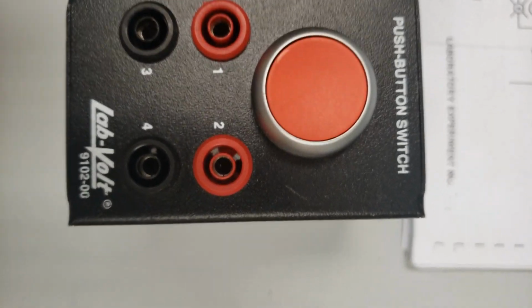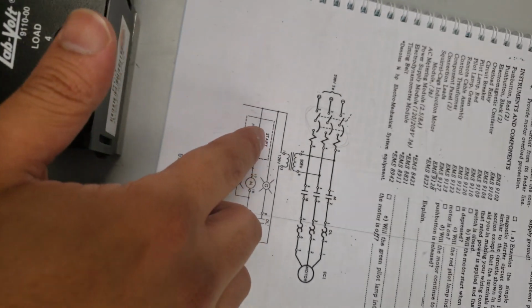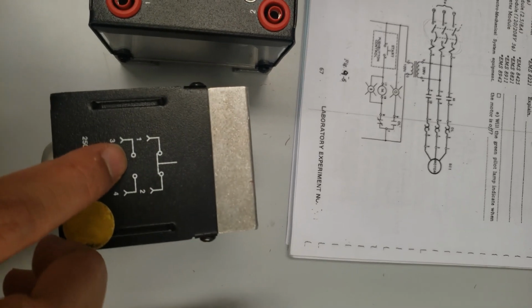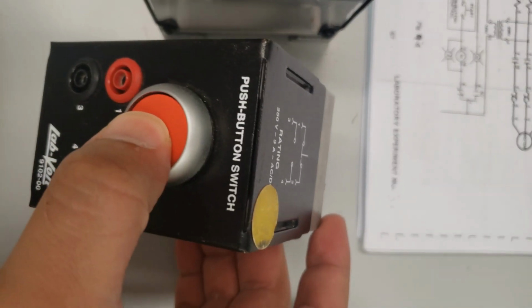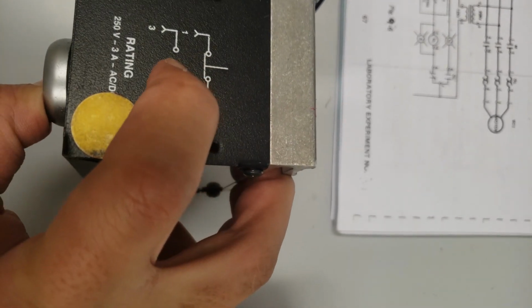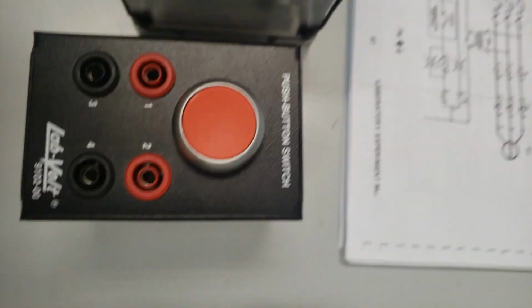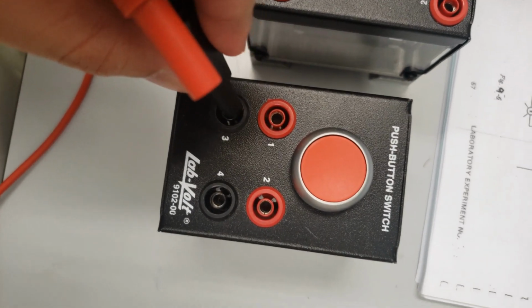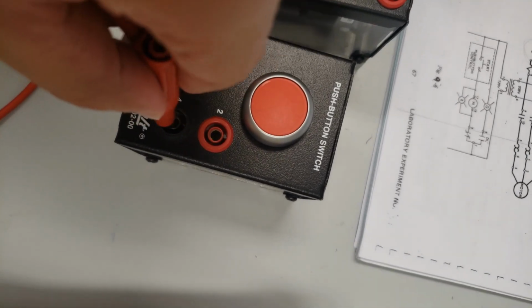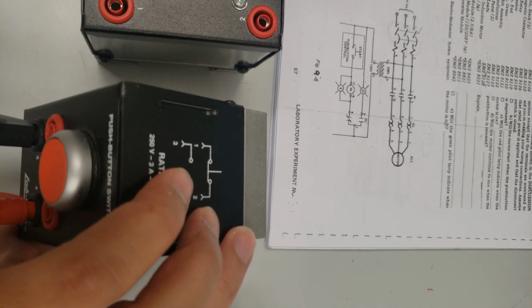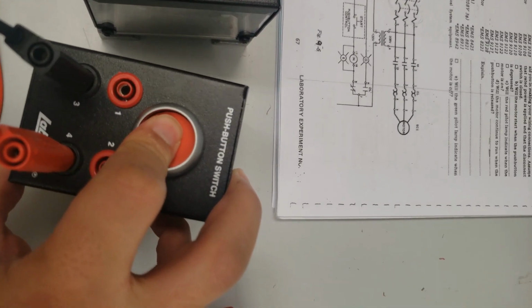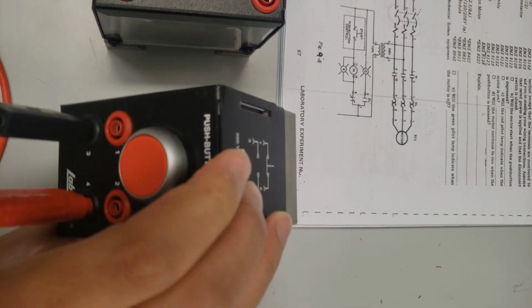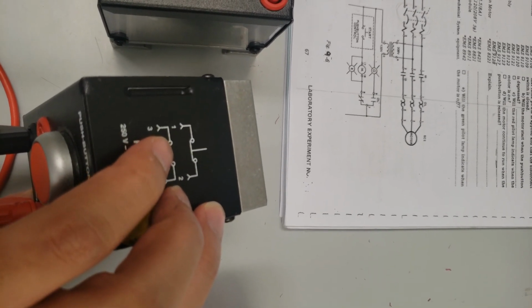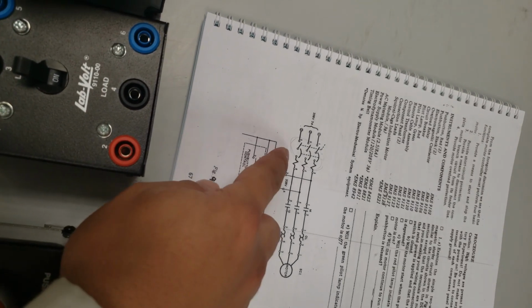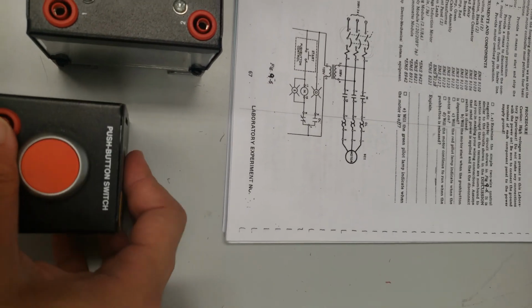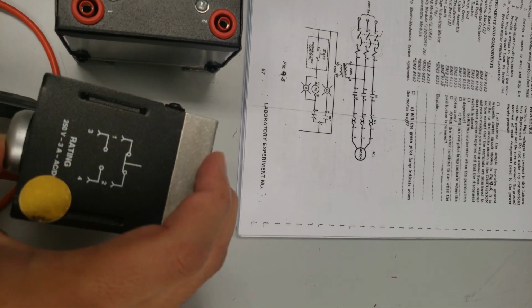This is the start push button. We've used 3 and 4. This one, 3 and 4, is normally open by default. Unless we press the start push button, this one will go down to connect both of these. So normally there is no connection between 3 and 4, because it's open. But if I press this one, the connection will come. If I release my finger, the connection will go. So 3 and 4 is open by default, so nothing happens here, unless I press the button, then the connection will come.